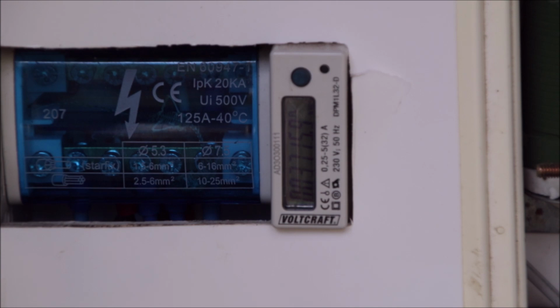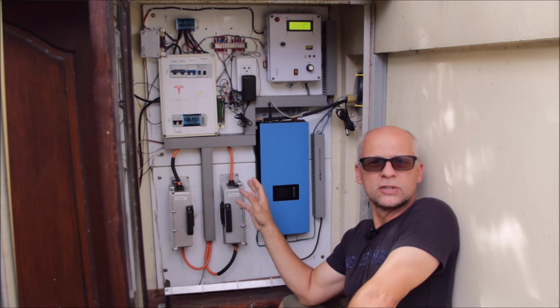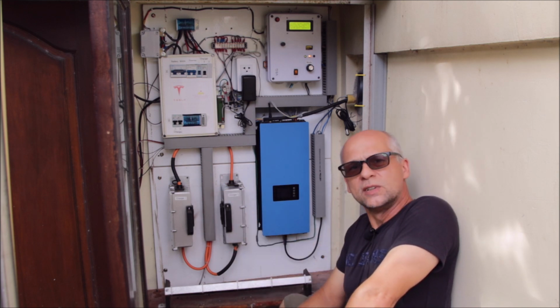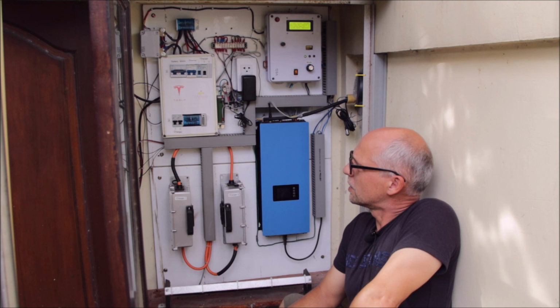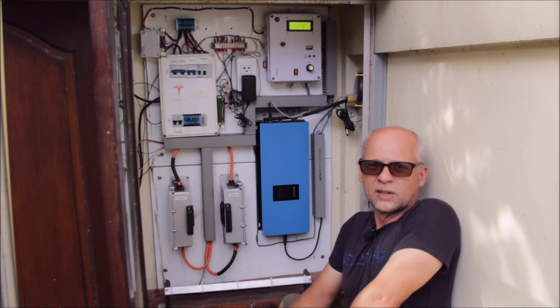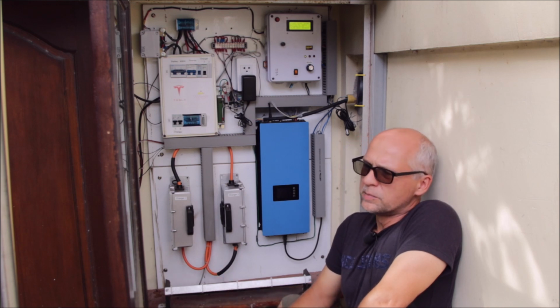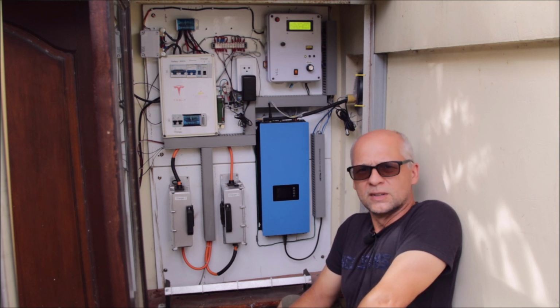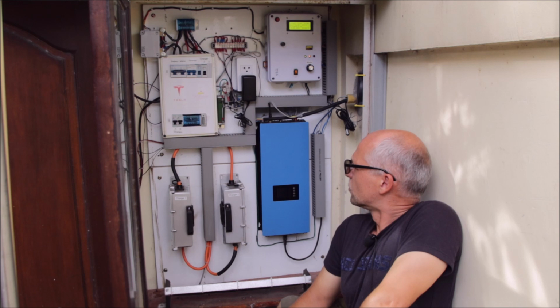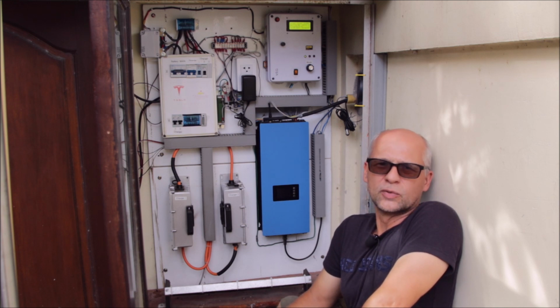So that's quite substantial. From the AC which I'm removing by the chargers, of course, only initially 93% will end up as DC in the battery, and then later by converting it back to AC we are again losing around the same amount of energy. But the round trip efficiency is around 85%. From the 3.7 megawatt hours which we have removed, we have then put back around 3 megawatt hours of AC into our behind the meter system here, and that in around 1 year has saved us about $350 US. So over the year it will be somewhere around $400.